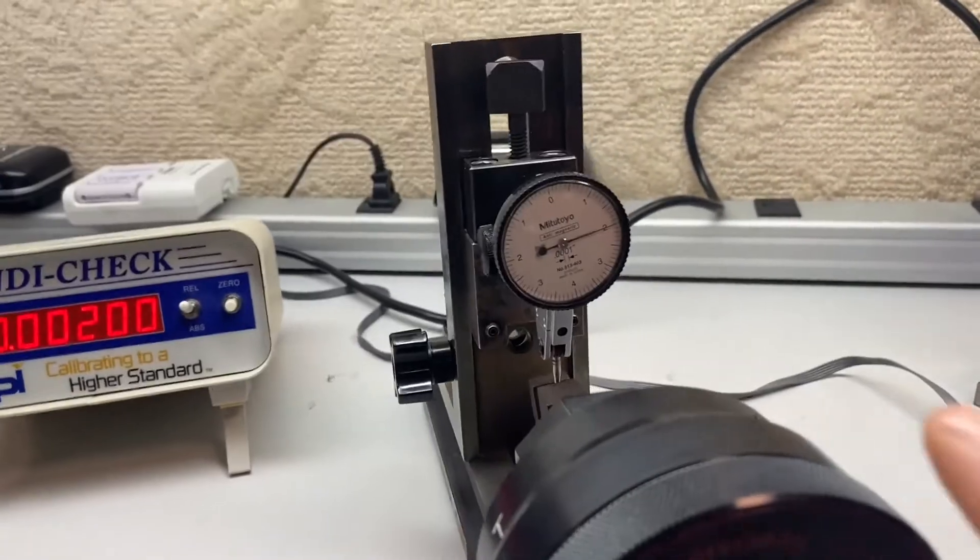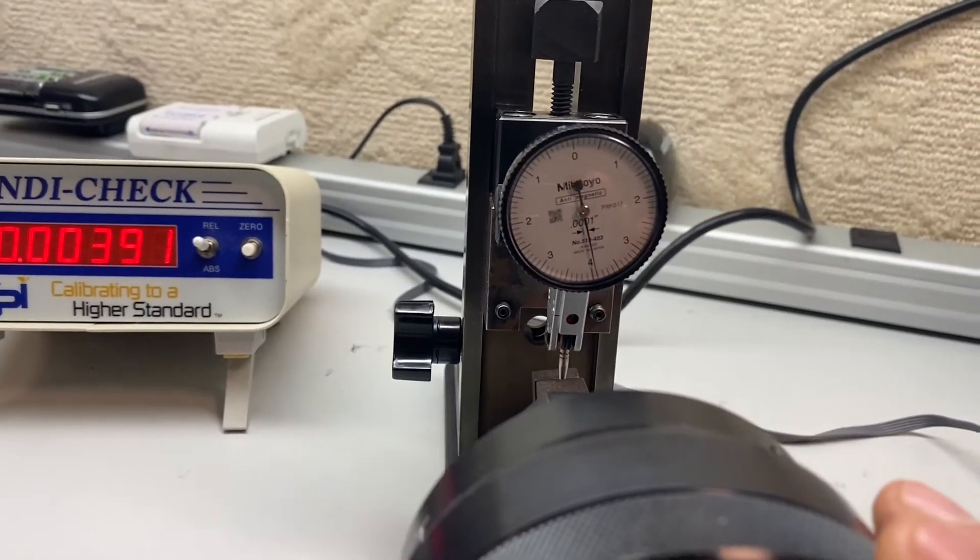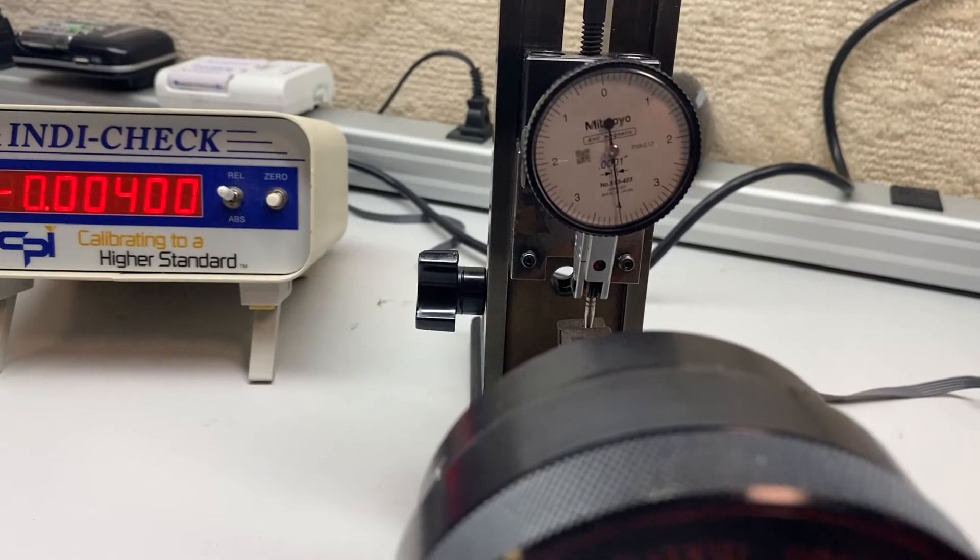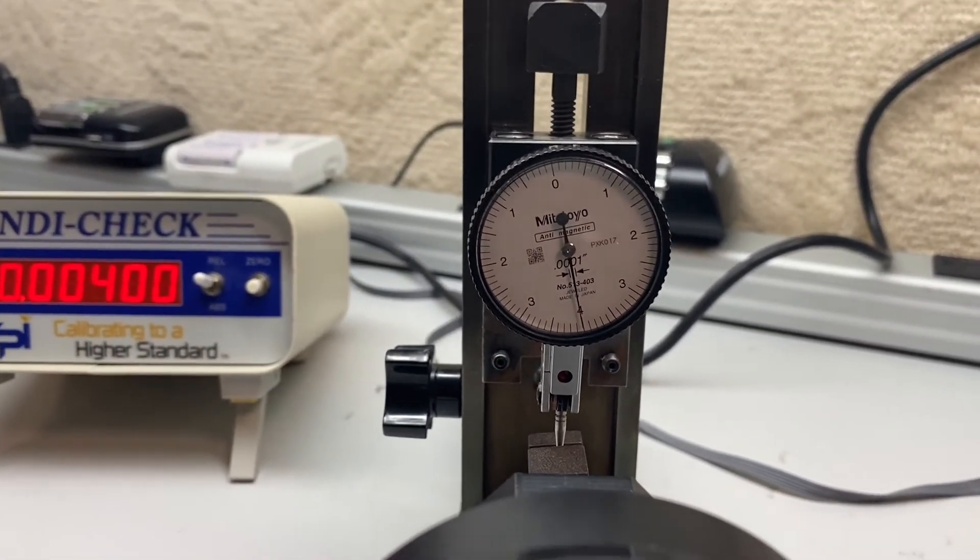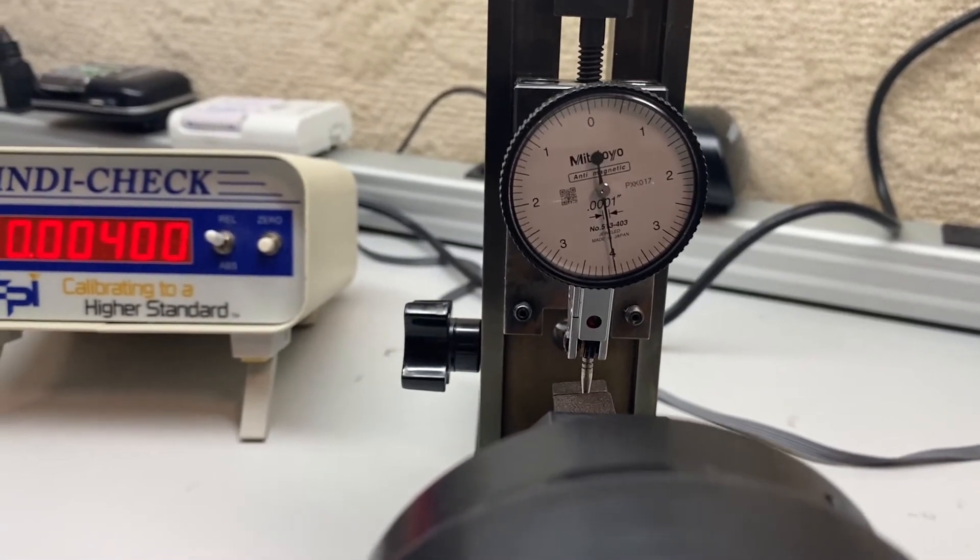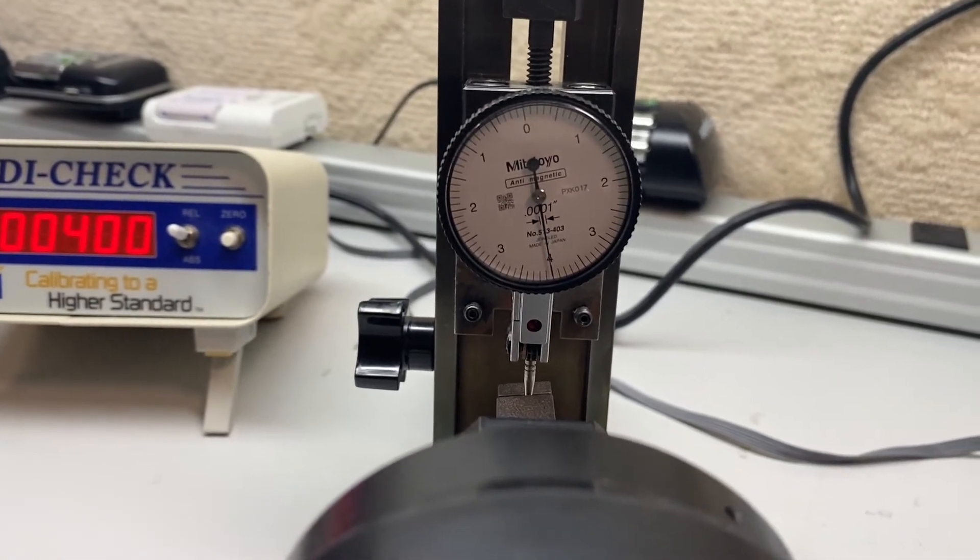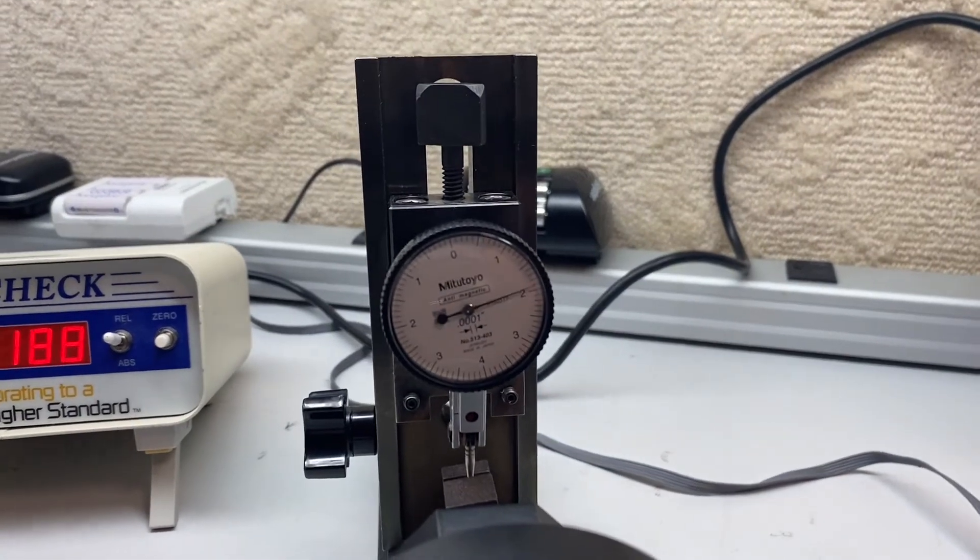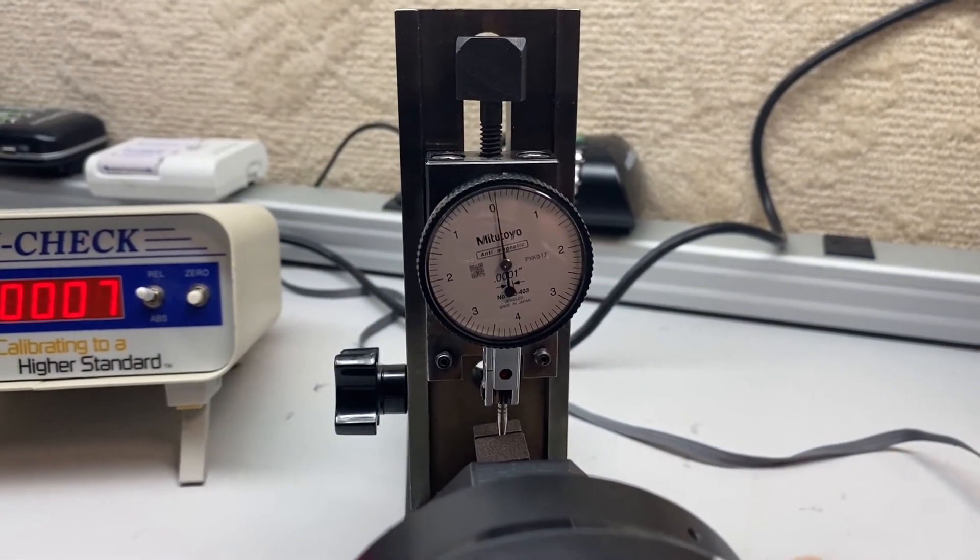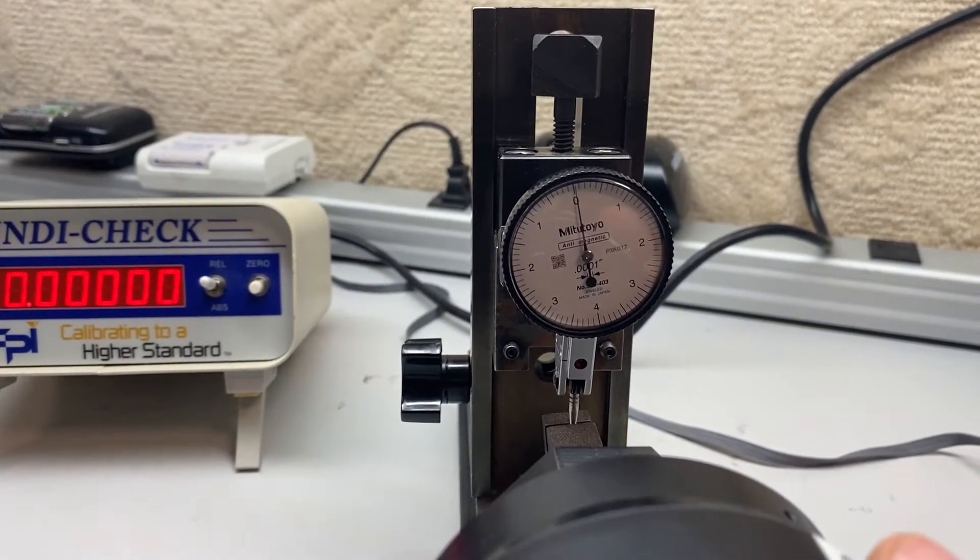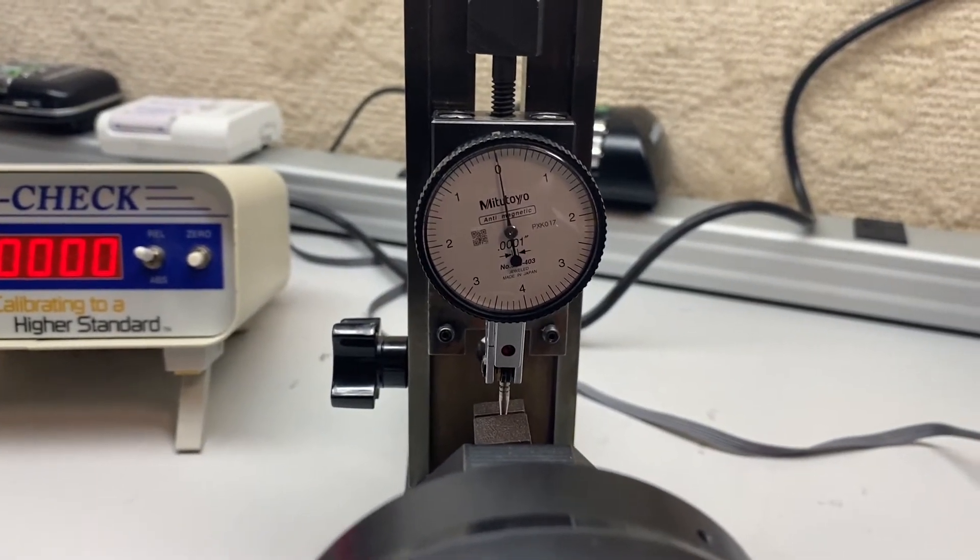And come all the way up to its full scale and we'll just say that that's four. Drive that Indi-Check all the way and take our reading. It's looking pretty good once you get dead on. You got to kind of check for parallax error. And then we'll begin to come back to our original zero. Taking data points on the way up and on the way down. Return and we'll check our zero. Zero is pretty good.